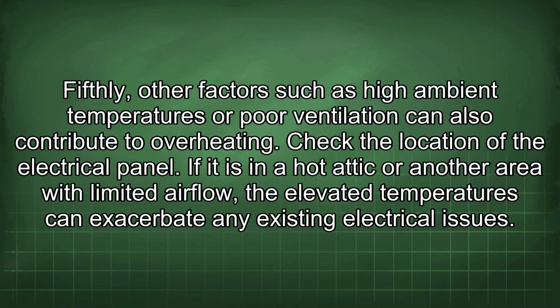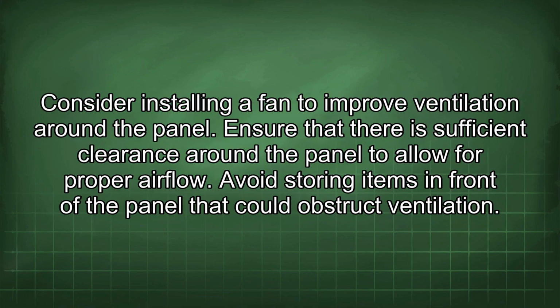Fifthly, other factors such as high ambient temperatures or poor ventilation can also contribute to overheating. Check the location of the electrical panel. If it is in a hot attic or another area with limited airflow, the elevated temperatures can exacerbate any existing electrical issues. Consider installing a fan to improve ventilation around the panel. Ensure that there is sufficient clearance around the panel to allow for proper airflow. Avoid storing items in front of the panel that could obstruct ventilation.